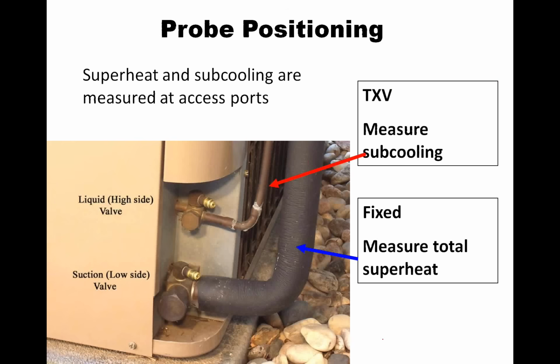When we talk about where we position our probes, the probe positioning is critical to proper operation. You've got to remember, we're always limited in where we put the probes by where we have points to measure pressure. There are pressure drops in the line, and it's really important, if you're going to try to quantify superheat and subcooling, that you measure pressure and temperature at the same location. So if we're talking a TXV system, we're going to measure subcooling at the condenser outlet. That's typically the only place we have a port to measure pressure, right?